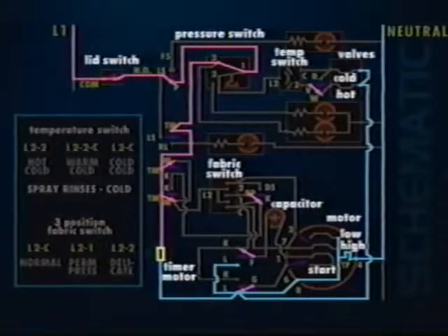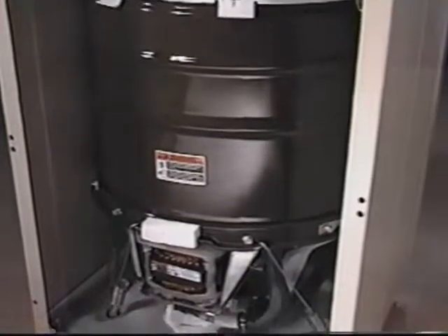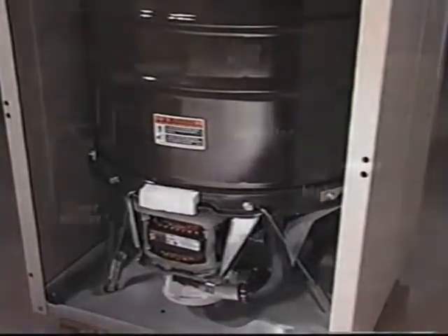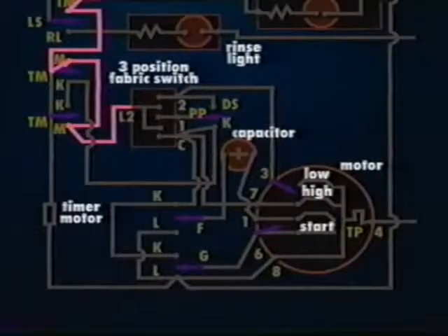The fill circuit is opened and the voltage is now present at terminal TM on the timer. With voltage to the timer motor, the timer will now begin to advance. Let's follow the current flow to the motor run and start circuits in agitation. Line 1 is routed through TM to M to L2 on the fabric selector switch.